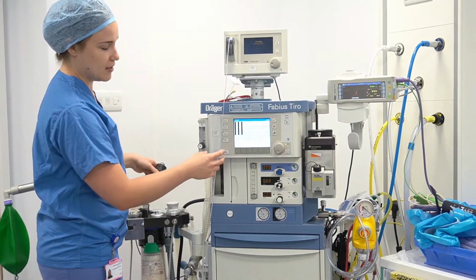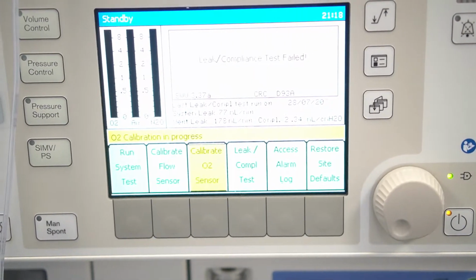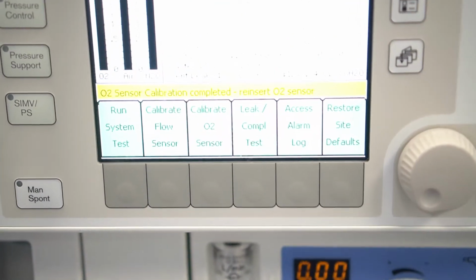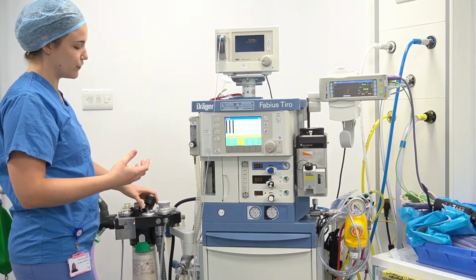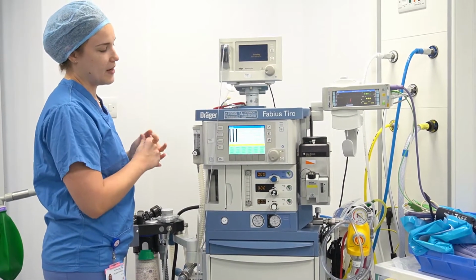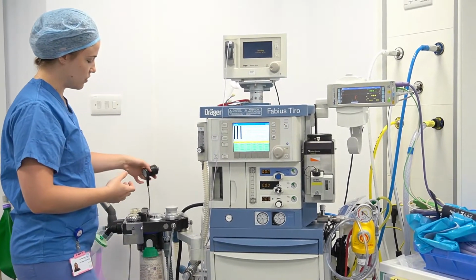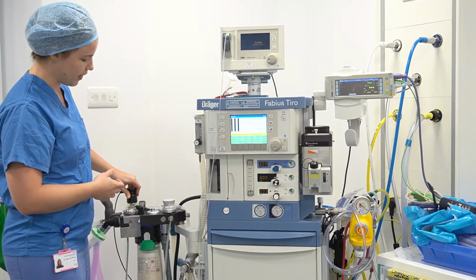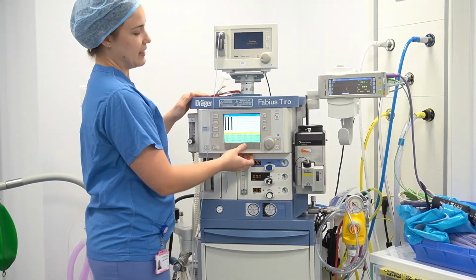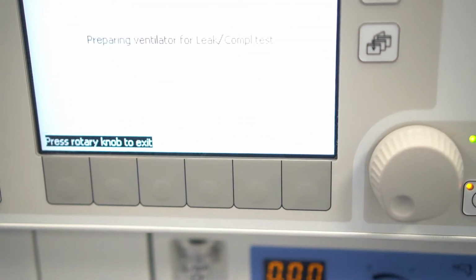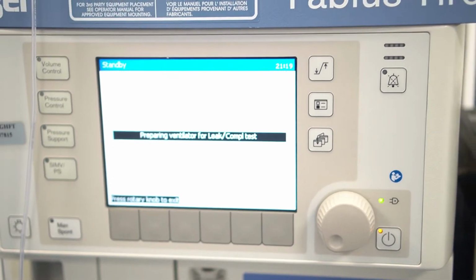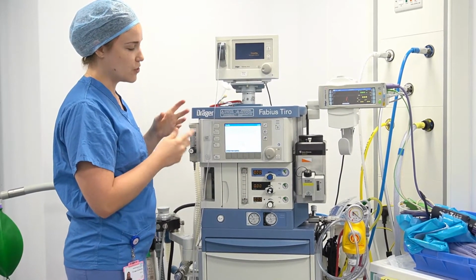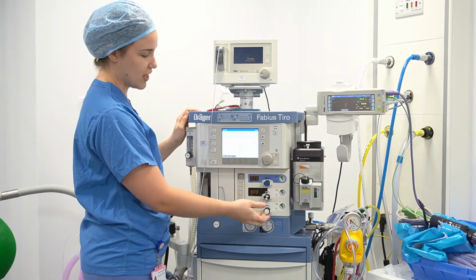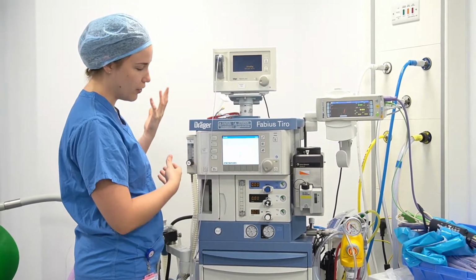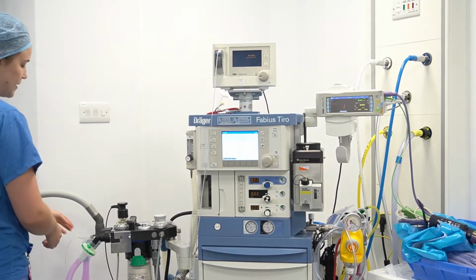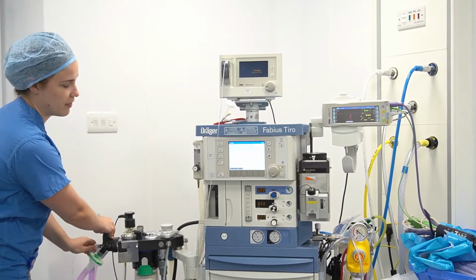So now to start the O2 calibration, you're going to again push the rotary knob, and then it's going to calibrate by itself. And again, once that's complete, it's going to tell you to reinsert the O2 sensor, so you can just pop that back on over there. Then we're going to do our leak and compliance test. It's going to give you a list of instructions again. First of all, close all the fresh gas control valves. As we can see, they're all on 0, they're all closed. And then place the Y piece on the plug located by the bag mount.